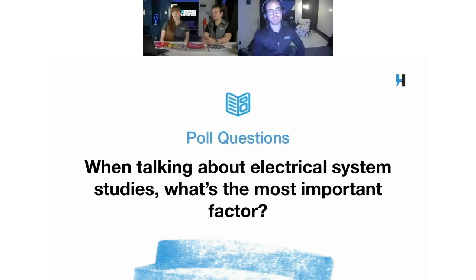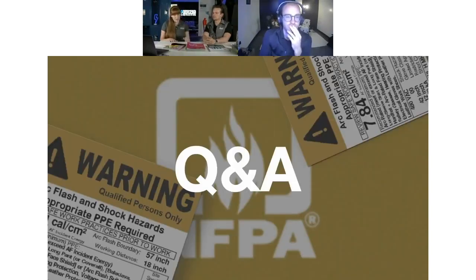The short circuit studies and coordination studies, honestly all of the ones we've mentioned today, are in Chapter 6 of NFPA 70B, 2023 edition, which is now a standard and shall be followed. Each section covers single line diagrams and system studies. Single line diagrams shall be maintained and kept accurate. Short circuit studies shall be updated and reviewed at intervals not to exceed 5 years or anytime there's a change. The same applies for coordination studies, load flow studies, reliability studies, and arc flash analysis. There's also section 6.8, electrical maintenance related design, requiring you to review all these studies and information before making a change.